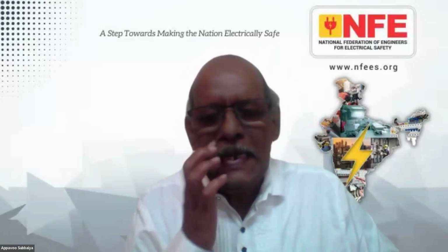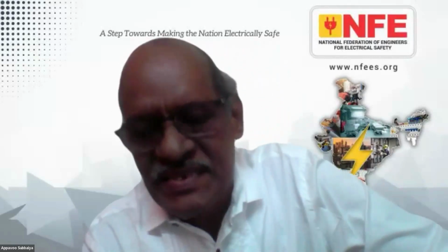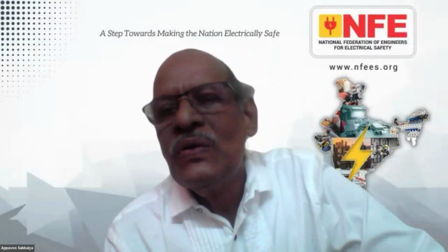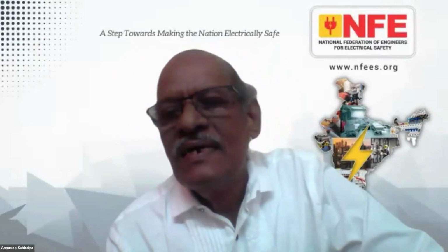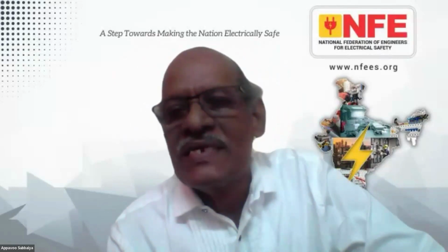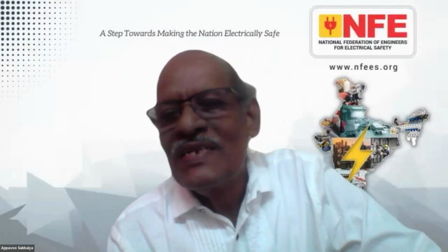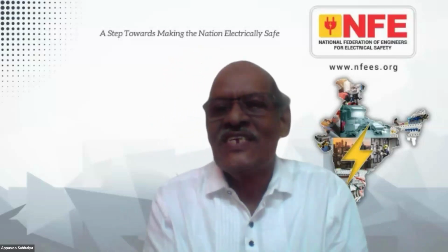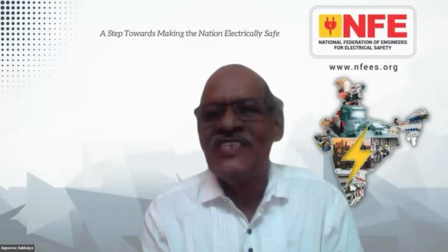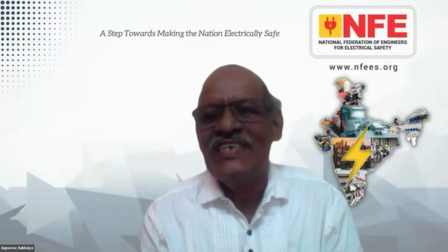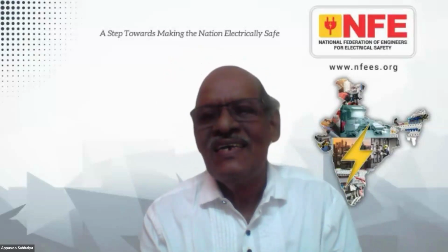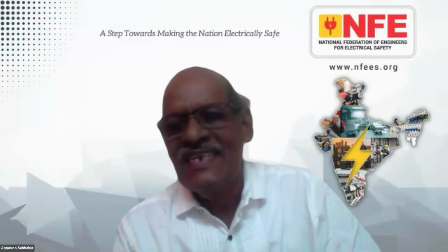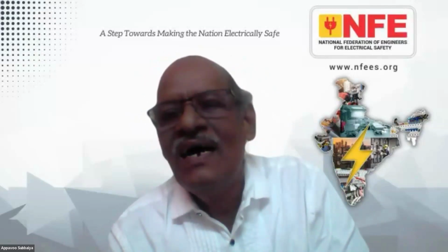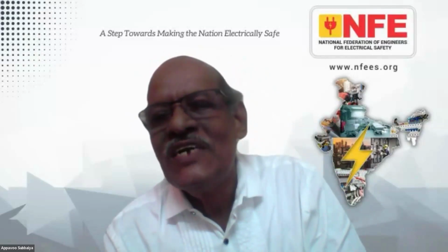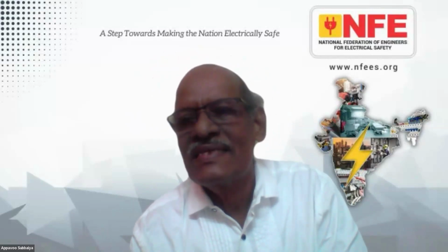Mr. Sunil Kumar VK, please go to our website to learn the fault loop impedance testing measures, methods and calculations. It's simply the voltage divided by the resistance of the fault path. The fault path is contributed by the supply conductor, and the return conductor is protected at the terminal, then the source. So if you provide a low enough loop impedance, your fault clearing device will trip. It's a logic, another subject you're invited to explore further on our website.